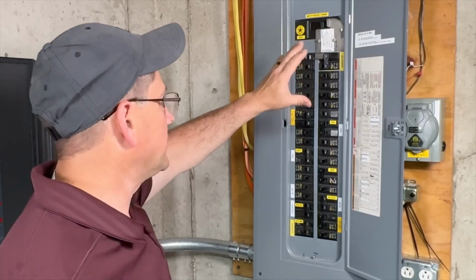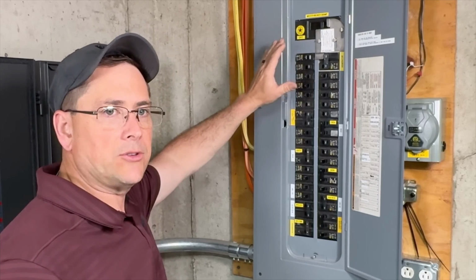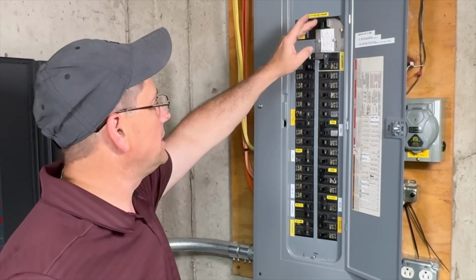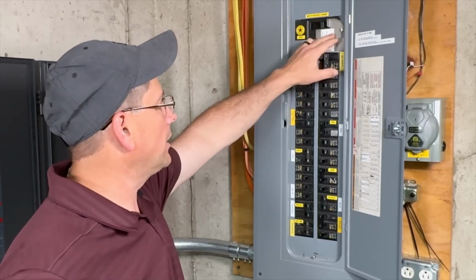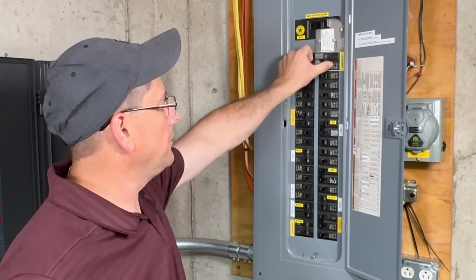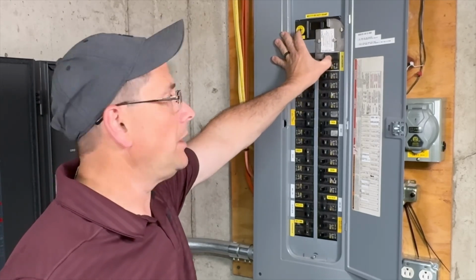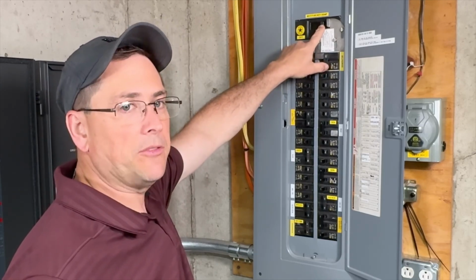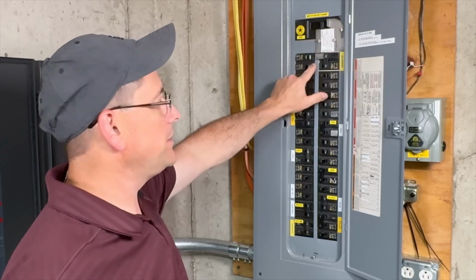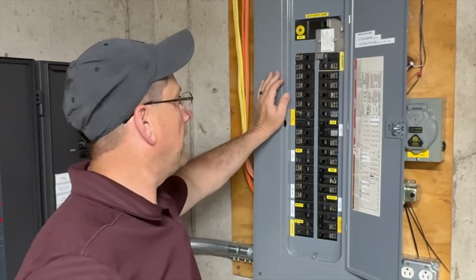This is probably the cheapest way to put in a whole house connection point, because when you install this little piece of metal, it prevents the generator from turning on — right now that's blocking it. So you have to turn off the main first, shove that up, and then you can flip it over. I've got the studio lights turned off, and now we're going to turn off the master breaker for the whole house.